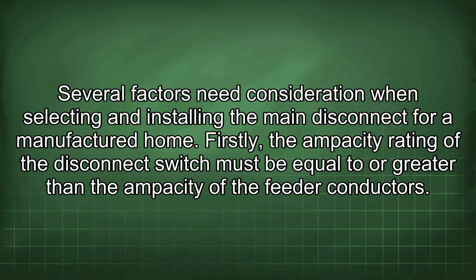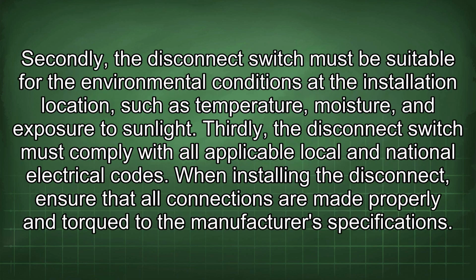Several factors need consideration when selecting and installing the main disconnect for a manufactured home. Firstly, the ampacity rating of the disconnect switch must be equal to or greater than the ampacity of the feeder conductors. Secondly, the disconnect switch must be suitable for the environmental conditions at the installation location, such as temperature, moisture, and exposure to sunlight. Thirdly, the disconnect switch must comply with all applicable local and national electrical codes.